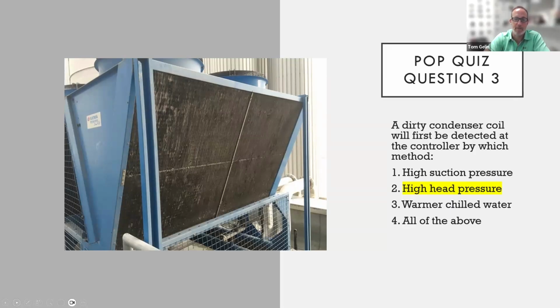If you had high suction pressure, it would be something to do with the evaporator. And of course, chillers will try to maintain the same chilled water temperature even when it's not performing well. So at some point, I suppose the chilled water will get warmer, but initially you'll get high head pressure would be the indication. Okay.